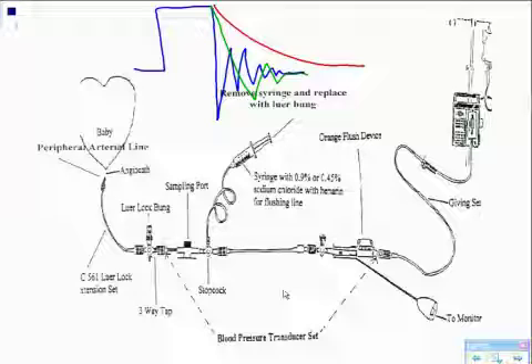No, two different things. Well, some people mix it up as two together. So maybe that's what they're teaching you, but really a resonance test is when you let go of it. The square wave test is when it goes up and stays there, and then you let go of it. That means that the measurement is exceeding your pressure measurement. So the square wave is in the top.